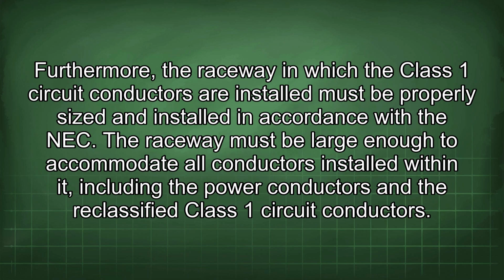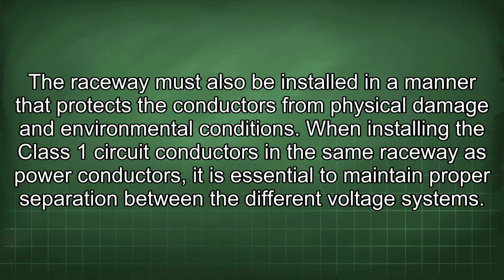Furthermore, the raceway in which the Class 1 circuit conductors are installed must be properly sized and installed in accordance with the NEC. The raceway must be large enough to accommodate all conductors installed within it, including the power conductors and the reclassified Class 1 circuit conductors. The raceway must also be installed in a manner that protects the conductors from physical damage and environmental conditions.